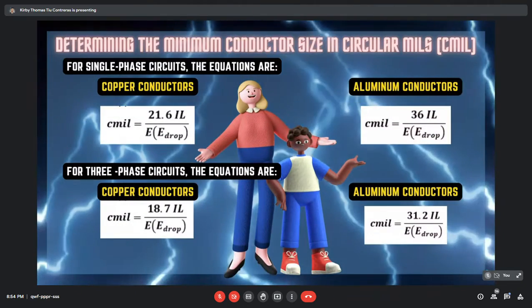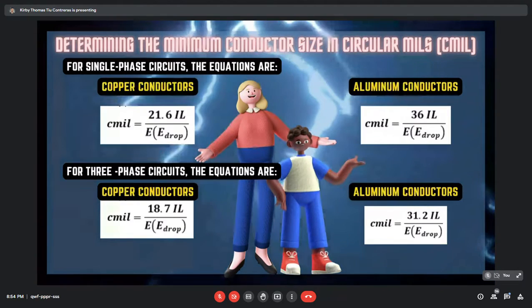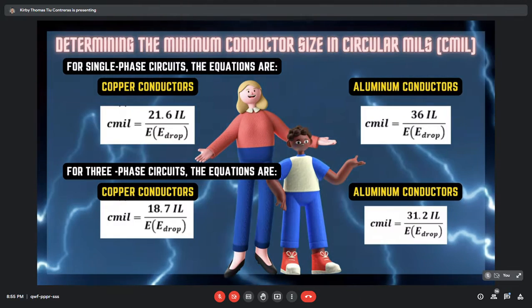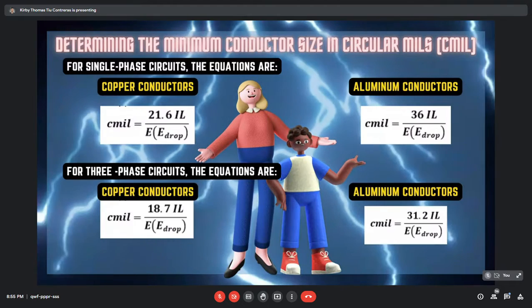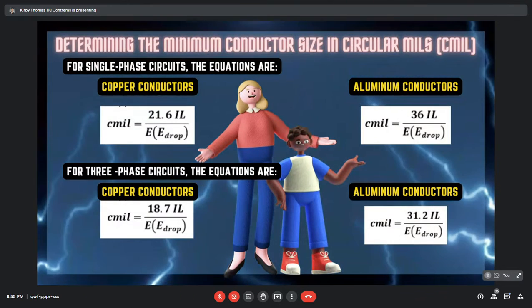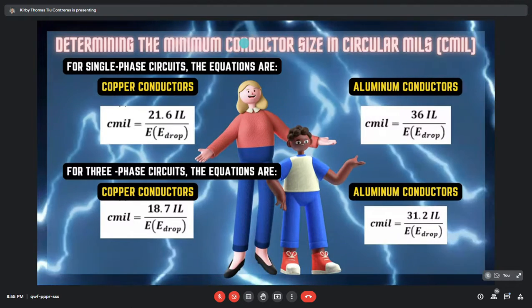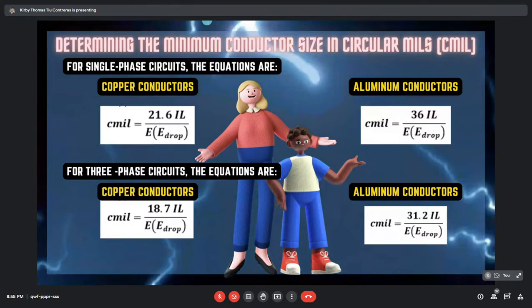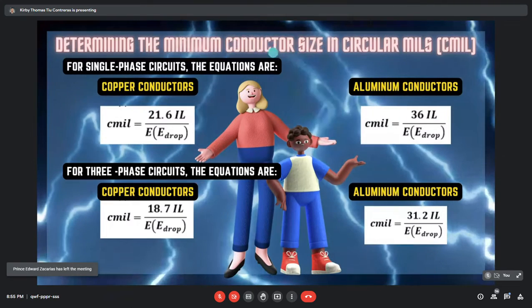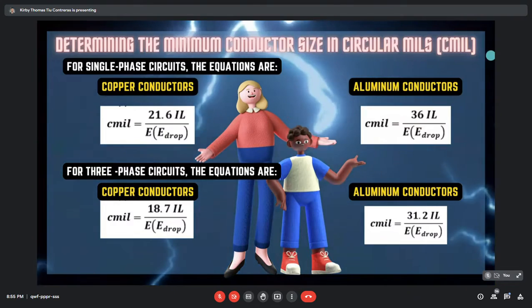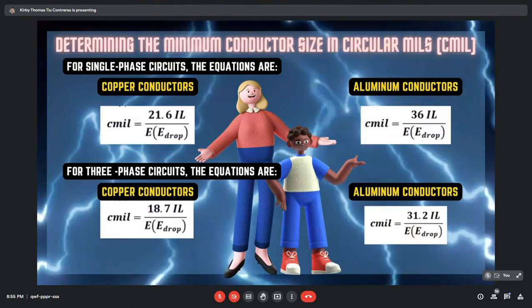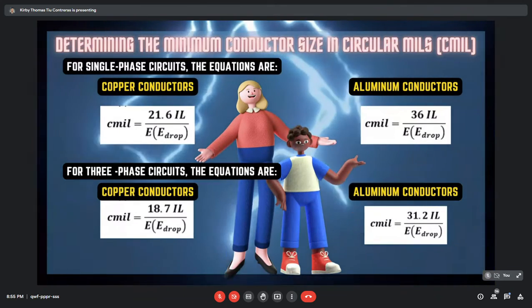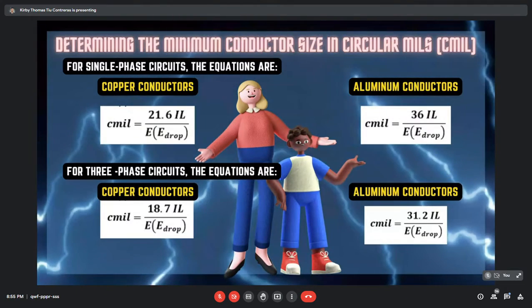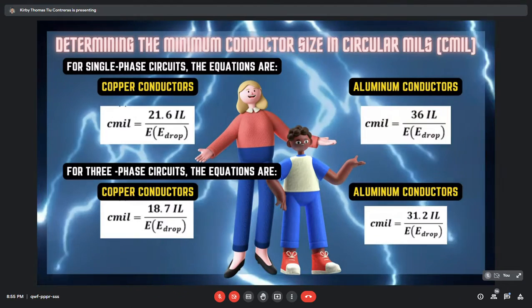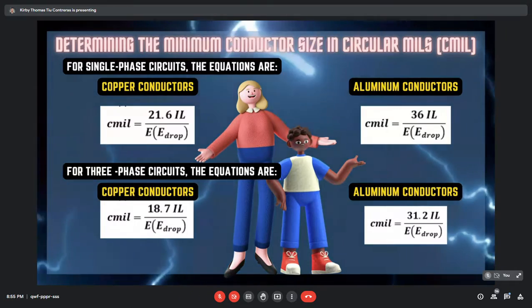Next, determining the minimum conductor size in circular mils. These formulas are derived from the ones we used for the maximum one-way distance of a conductor. For single phase circuits, for copper conductors, C mil is equal to 21.6 times I times L divided by E times voltage drop, and for aluminum conductors, C mil is equal to 36 times I times L divided by E times voltage drop. For three-phase circuits, for copper conductors, C mil is equal to 18.7 times I times L divided by E times voltage drop, and for aluminum conductors, C mil is equal to 31.2 times I times L divided by E times voltage drop. So let's have another example.